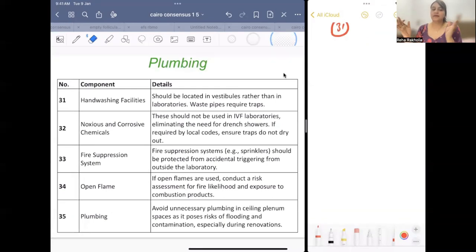Waste pipe required traps, like pipes and all should be enclosed. It should not be open. Then noxious and corrosive chemicals should not be used in the IVF lab. So we do not require a drench shower in the IVF lab. If required by the local code, ensure traps do not dry out.